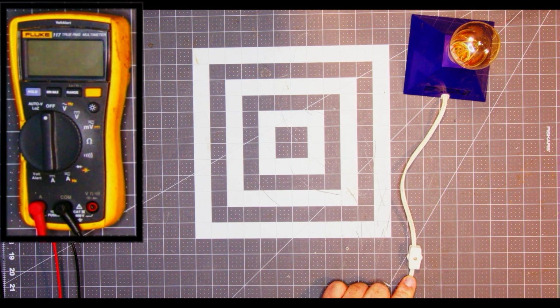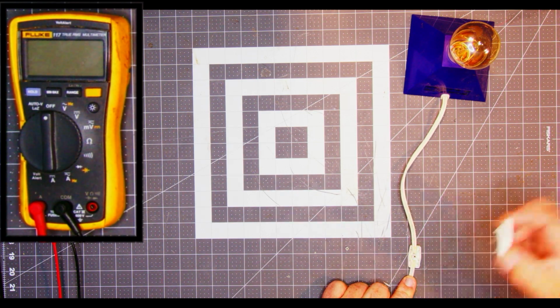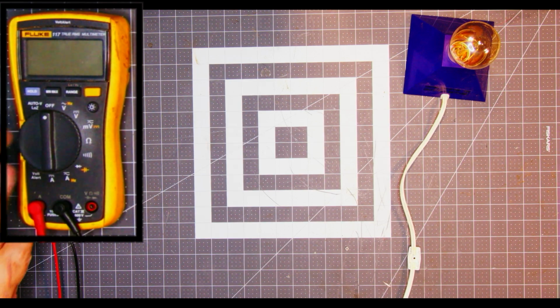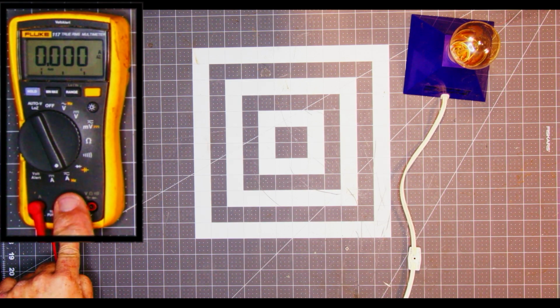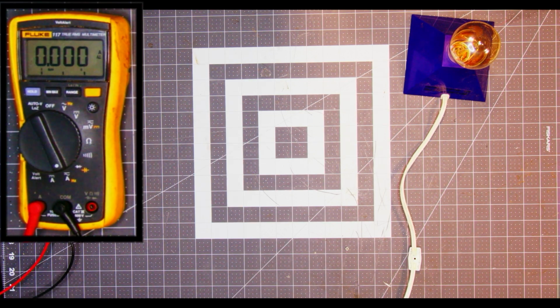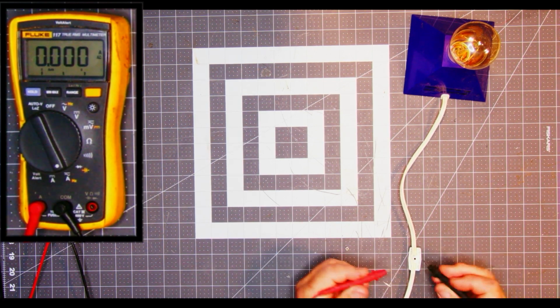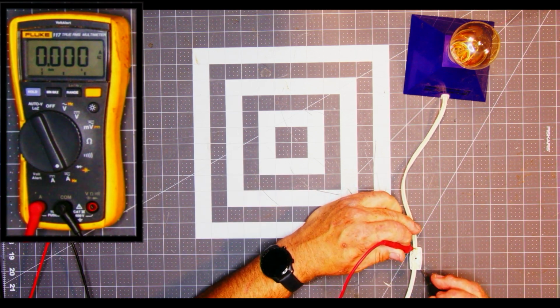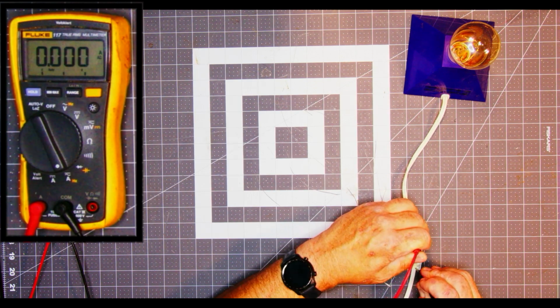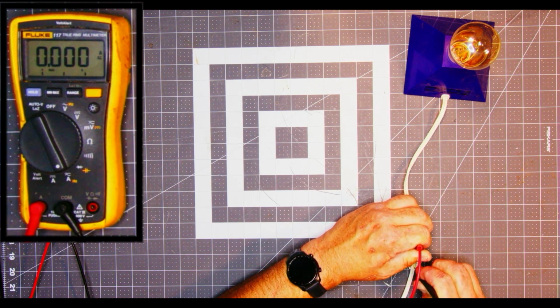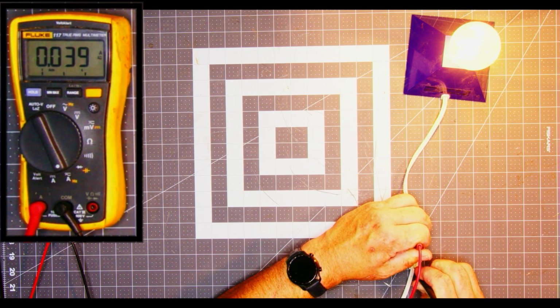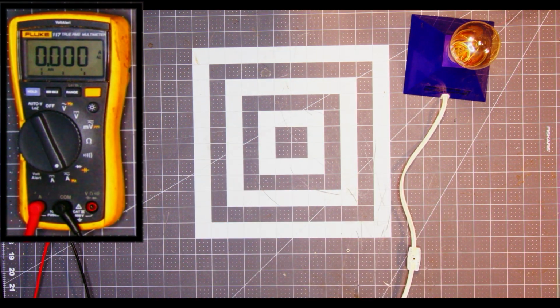We can test AC current the same way. In this case, I'll remove the switch from this light socket, select the AC current setting with the sine wave. Make sure our probes are in the current configuration. And in this case, we're going to use the sharp ends of the probes to pierce the wire. We can see that this light bulb is using 0.03 amps. When we remove the meter, the circuit is open.